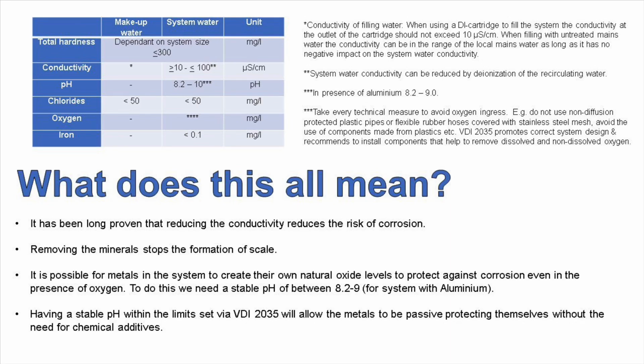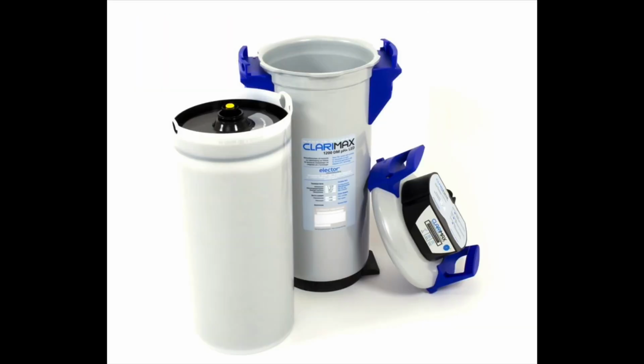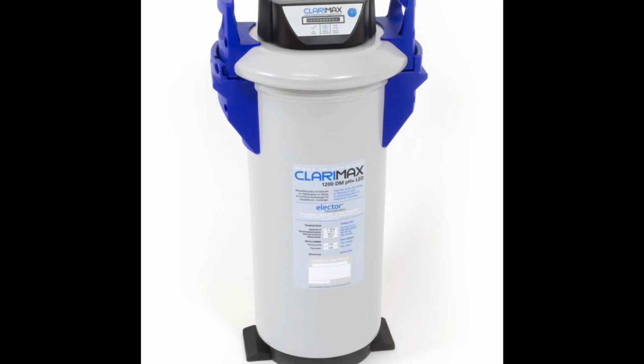You can actually increase the pH by boiling the system. If you have an air separator on the system and you're heating the water to above 60 degrees, it's called the self-alkalization zone. As the water is heated, the gases are released, the carbon dioxide is released, and the pH will naturally stabilise around 8.2, 8.5. It's something you'd want to monitor. It won't happen on the day you're there. It might take a couple of weeks, or a couple of months. But VDI allows one full heating season for this to happen, because if you fit a boiler in the summer, you might not be able to run the system long enough for this to happen while you're on site. But it will happen. Luckily, using a device like the Clarimax, we leave the system after commissioning already around 8.2, 8.5, so we know the system is already at the state we want before we've left site.